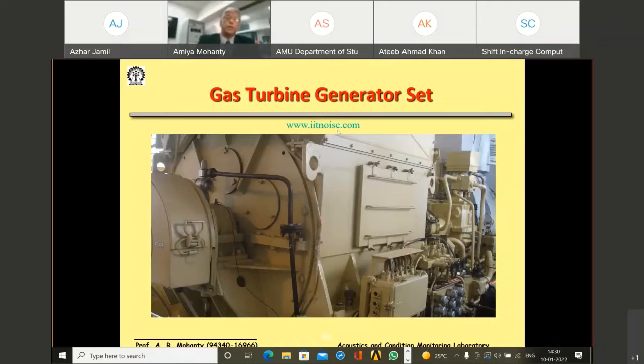So by monitoring the generator output, the ripples in the generator voltage, I can find out the characteristic fault frequency of the gas turbine. We also did this through vibration monitoring. This was about two decades ago which we did. So as you will tell, you get an idea.